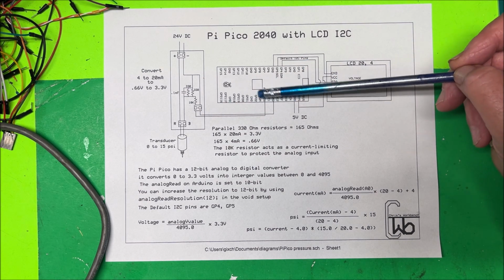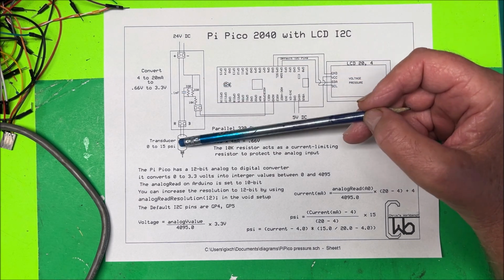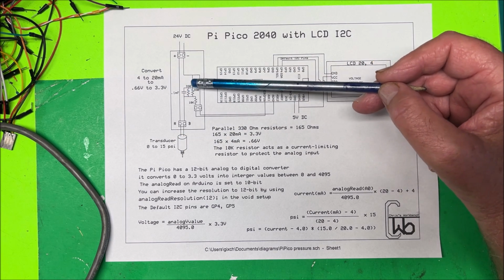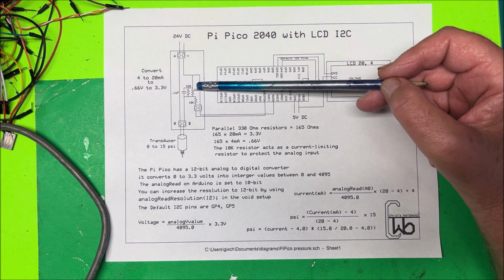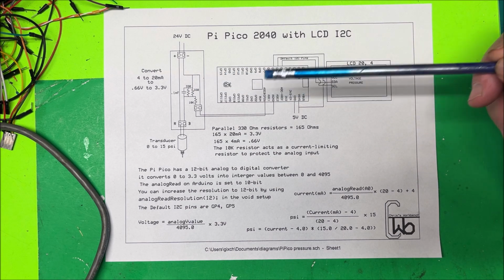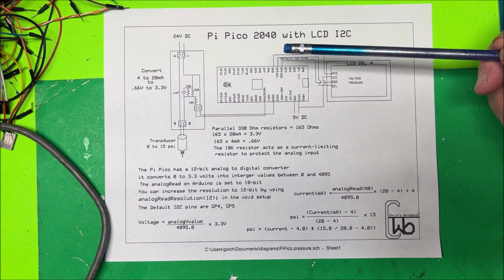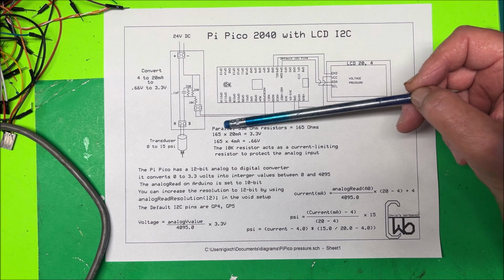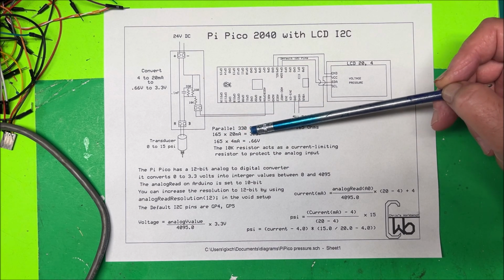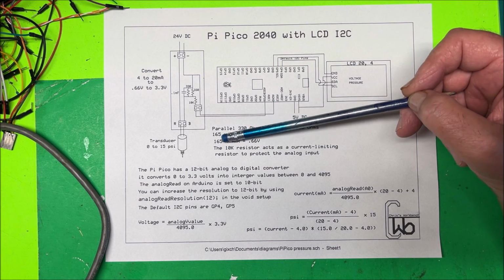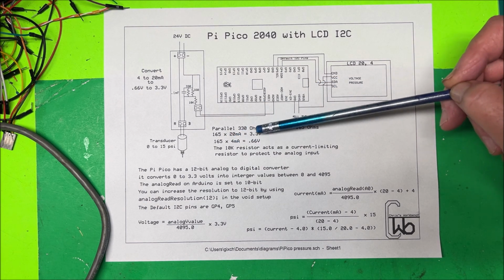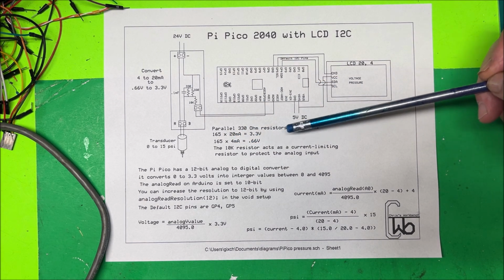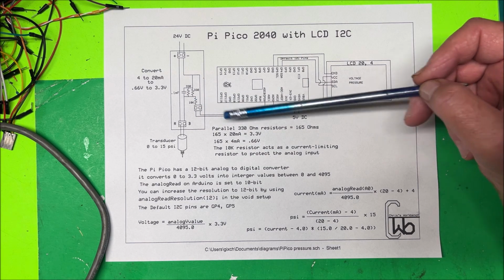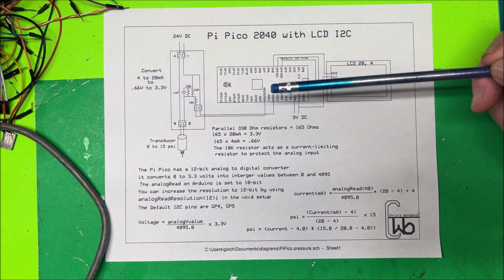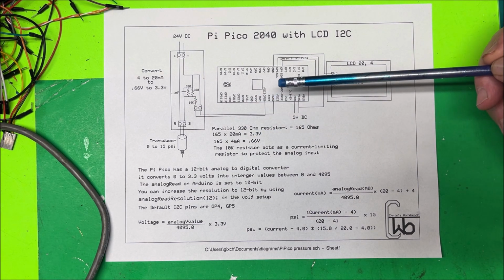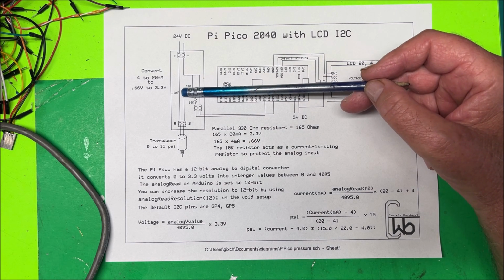But now, in order to convert the 4 to 20 milliamps to voltage, I have two 330 ohm resistors in parallel, and that makes 165 ohms. If you take 165 times your 20 milliamps, you get your 3.3 volts. And if you take 165 times your 4 milliamps, you get 0.66 volts. And then I've got a 10K resistor here, and that just acts as a current limiting resistor to protect the analog input, is all. And I have a capacitor across there.